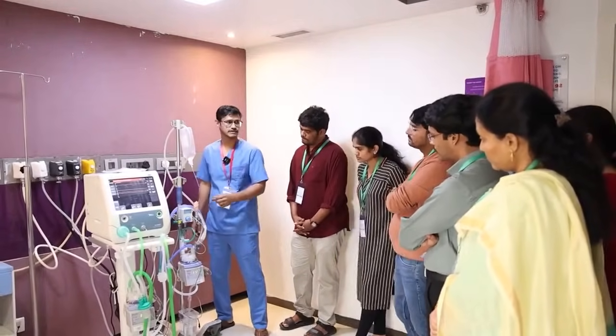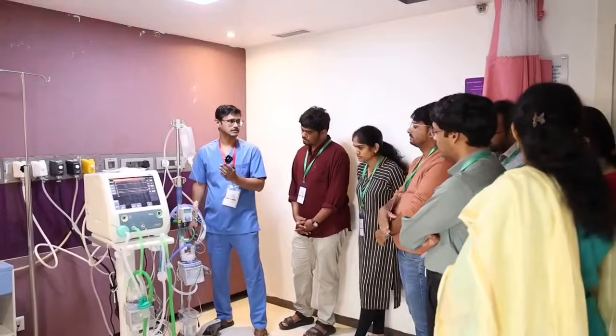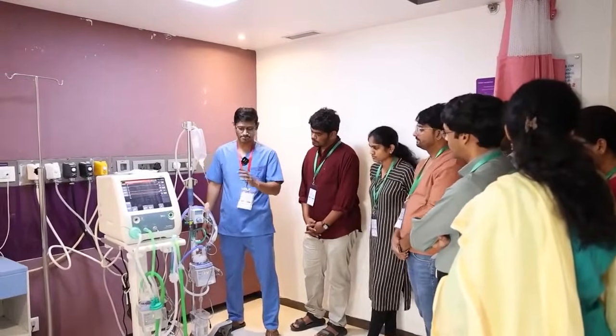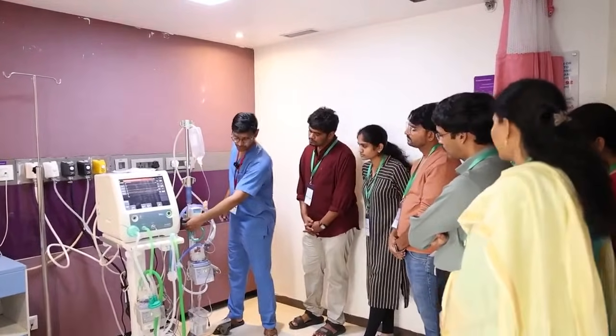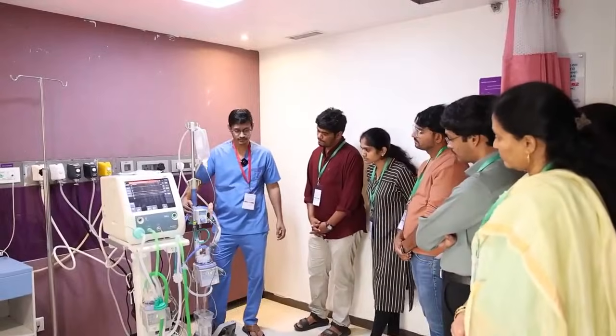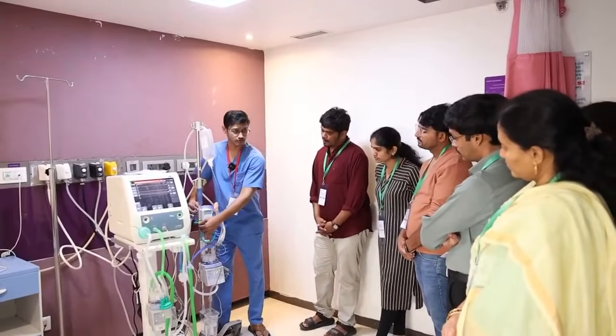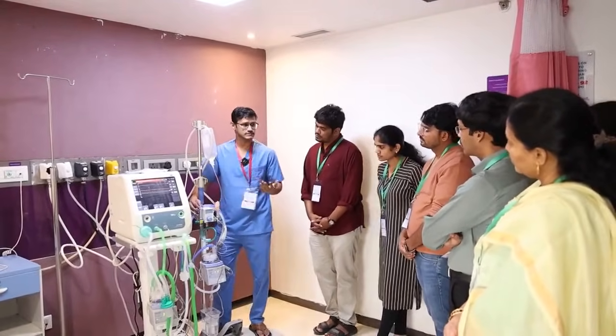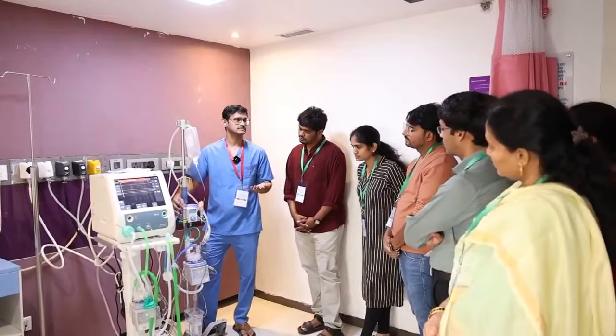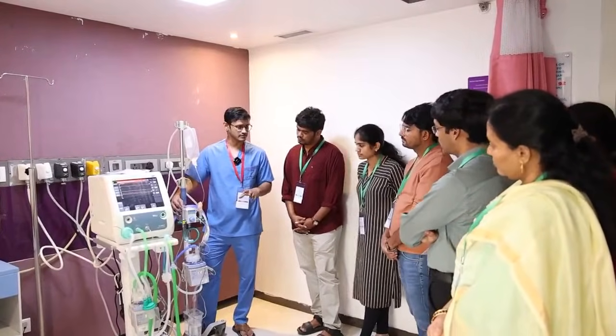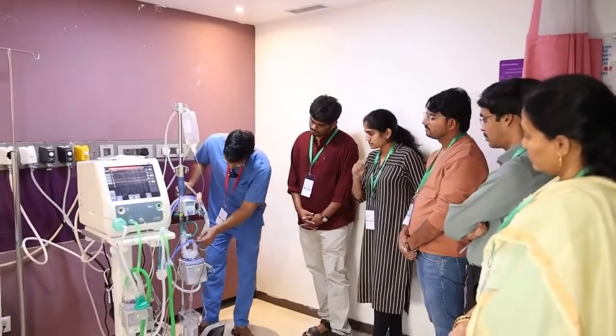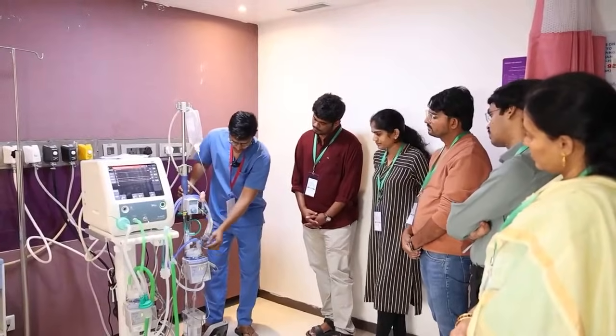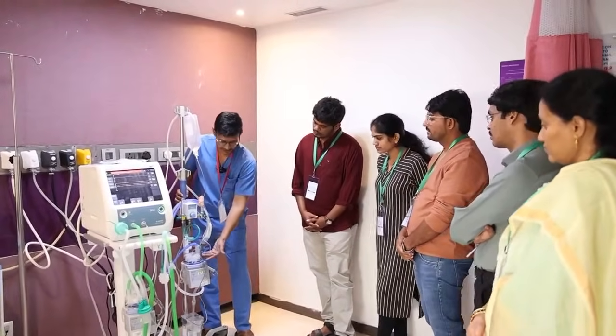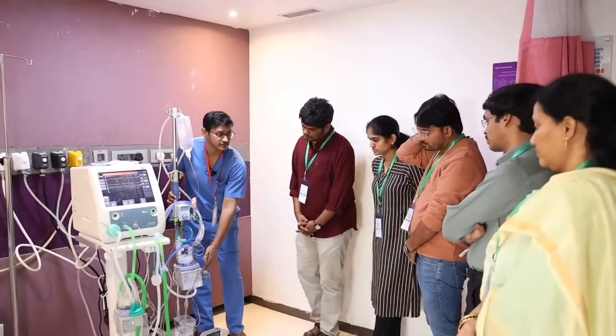You can titrate the FiO2, how much you want to deliver, from 21 to 100%. Then we have a tube, we have a flow meter which is attached to this blender. Here you can adjust the flow. Usually for CPAP we keep a flow of around 6, 7 or 8 liters per minute. And then from this flow meter a small tube goes into the humidifier. This is the humidification chamber and this is the humidifier.